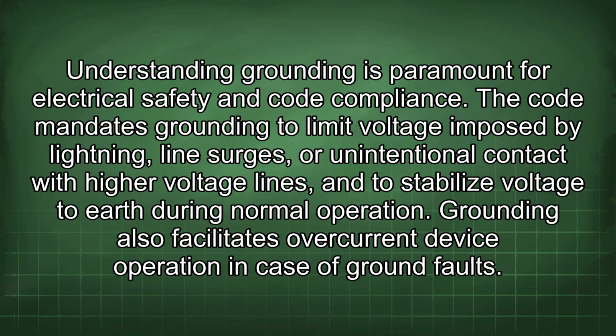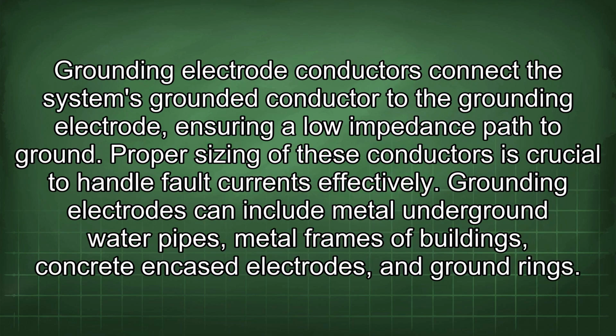Understanding grounding is paramount for electrical safety and code compliance. The code mandates grounding to limit voltage imposed by lightning, line surges, or unintentional contact with higher voltage lines, and to stabilize voltage to earth during normal operation. Grounding also facilitates overcurrent device operation in case of ground faults. Grounding electrode conductors connect the system's grounded conductor to the grounding electrode, ensuring a low impedance path to ground.